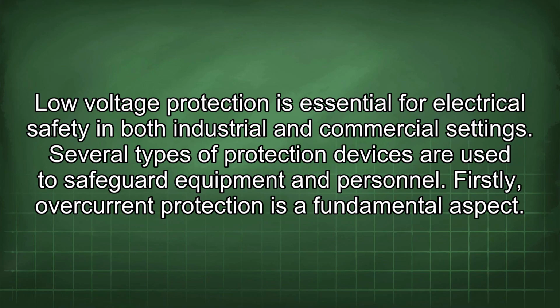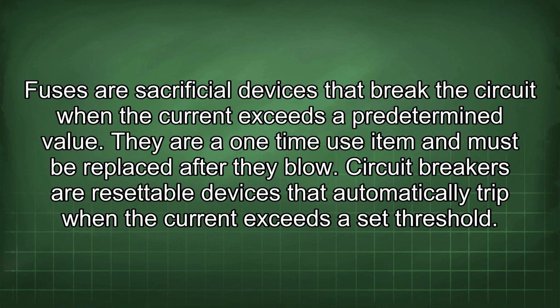Low voltage protection is essential for electrical safety in both industrial and commercial settings. Several types of protection devices are used to safeguard equipment and personnel. Firstly, overcurrent protection is a fundamental aspect. Fuses are sacrificial devices that break the circuit when the current exceeds a predetermined value. They are a one-time use item and must be replaced after they blow.